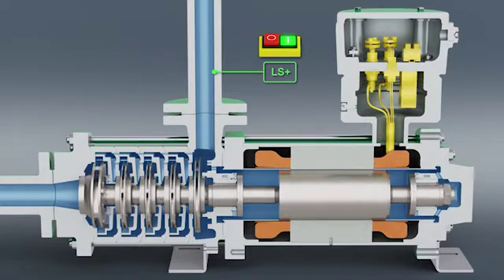A partial flow in the high pressure area of the pump is diverted from the last impeller and is used to cool the motor and lubricate the hydrodynamic slide bearings.